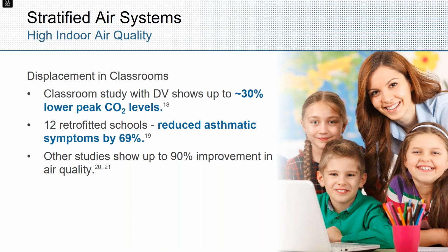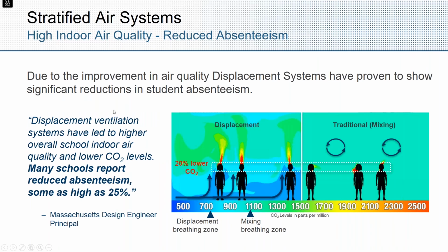The first study compares a run of displacement classrooms in the same school to classrooms across the hall with mixed-air ceiling supply. They noted significantly lower peak CO2 levels in the displacement spaces, naturally due to the effect shown in that smoke demonstration video, moving contaminants out of the breathing zone.